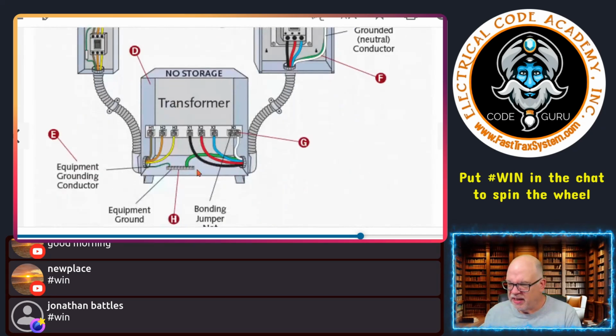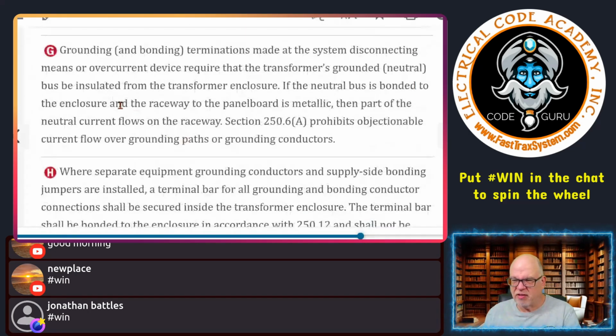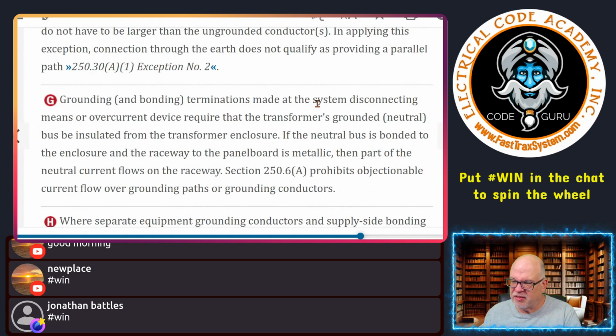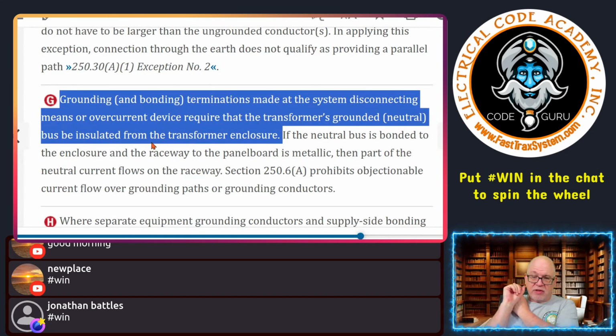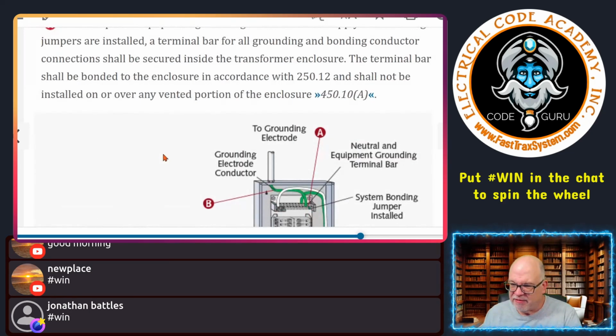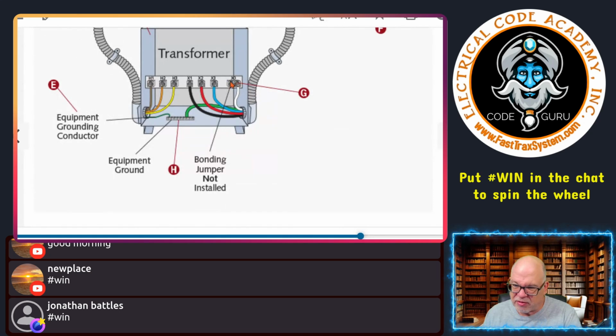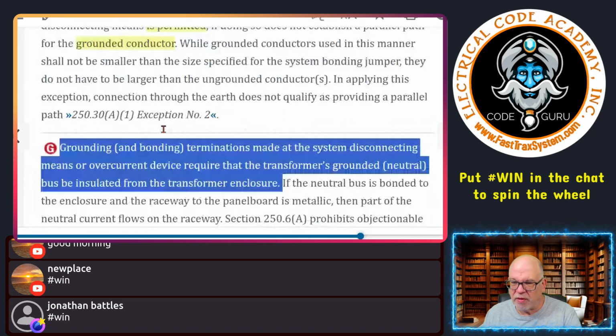G. So G is right here. So here's the XO in this transformer. In G, it says grounding and bonding terminations made at the system disconnecting means or the overcurrent device require that the transformer's grounded neutral bus be insulated from the transformer enclosure. So if you do want to make that connection over in the panel instead of in the transformer, that's fine. Remember what we said? You're not going to make this connection from here over to here. You're just going to leave out the system bonding jumper. Why? Because we did it right here. That's a no-brainer, right?